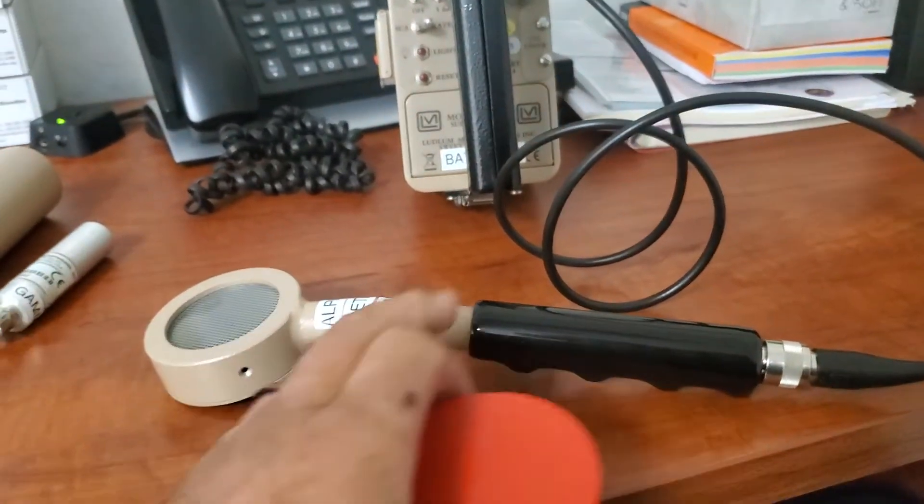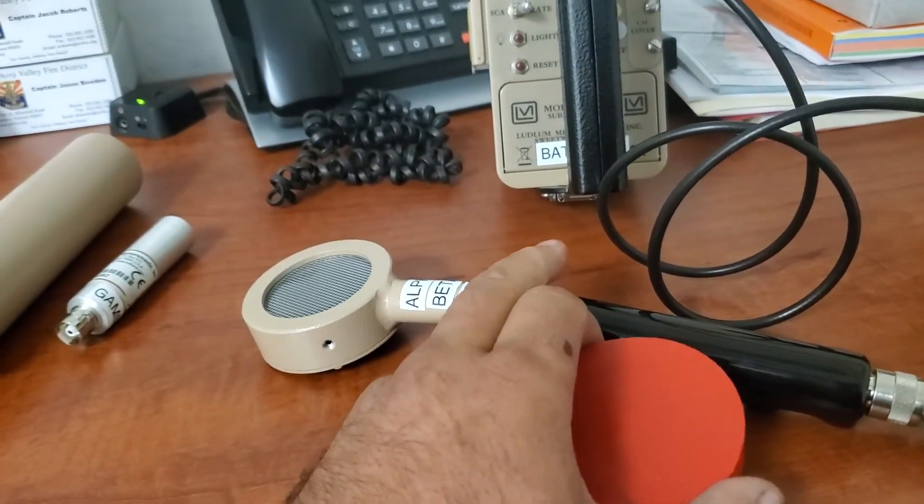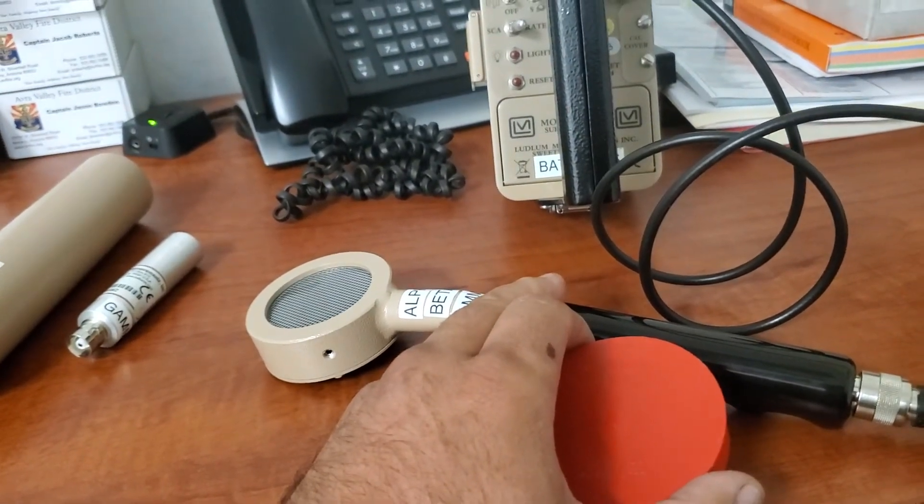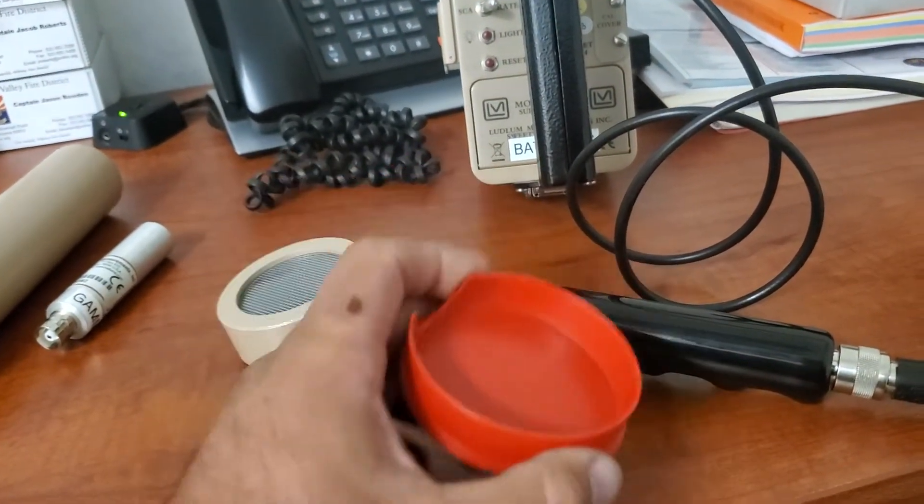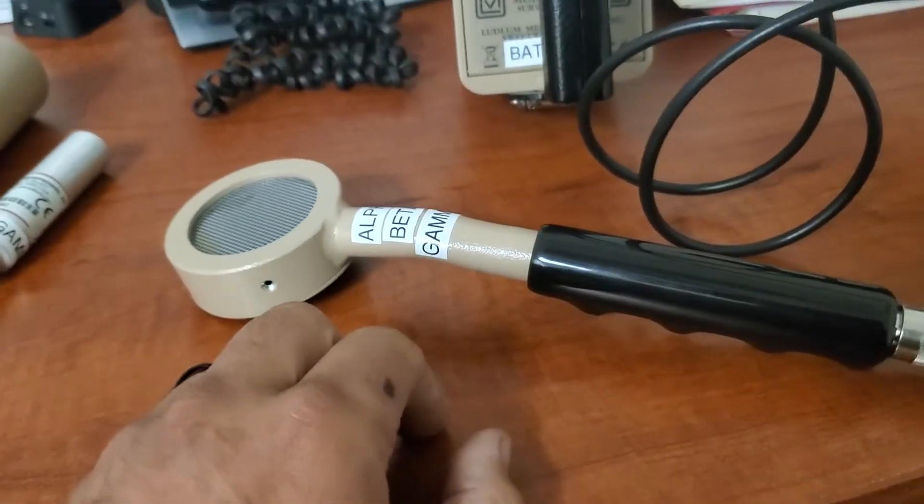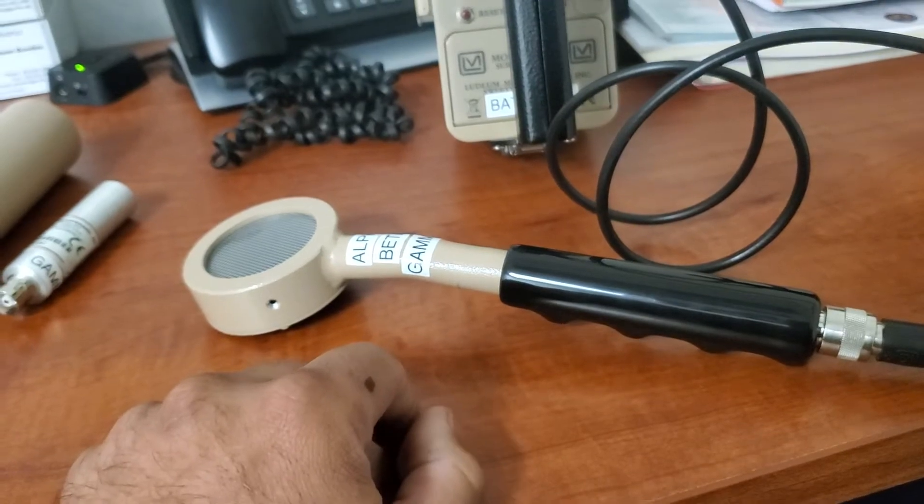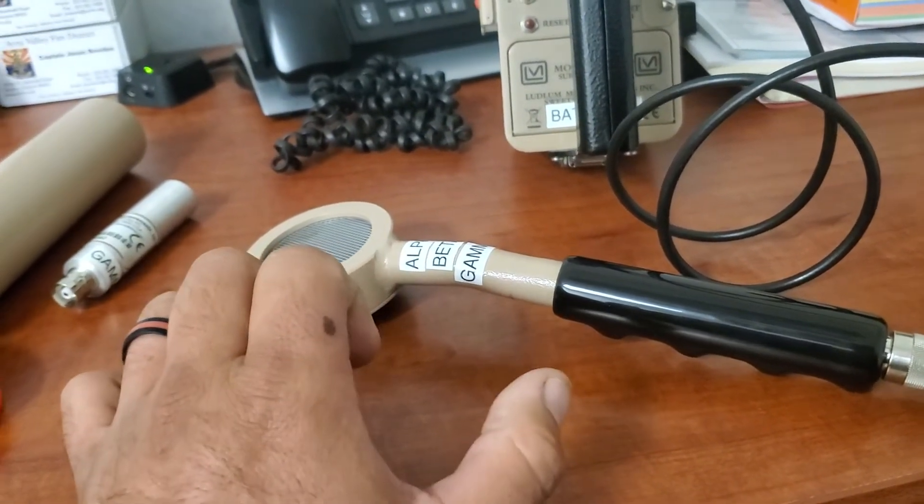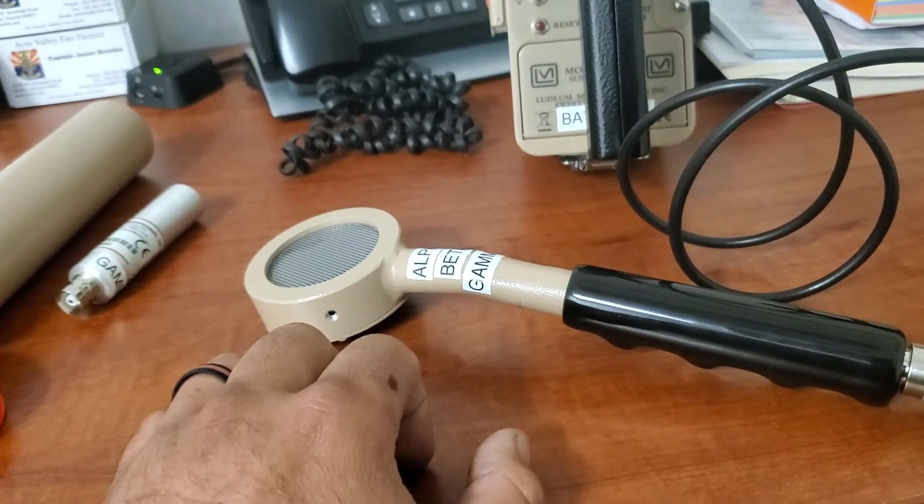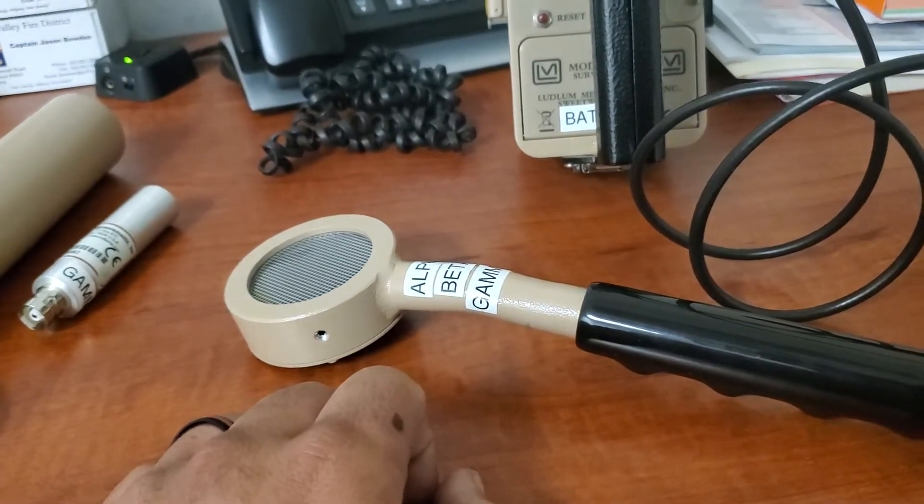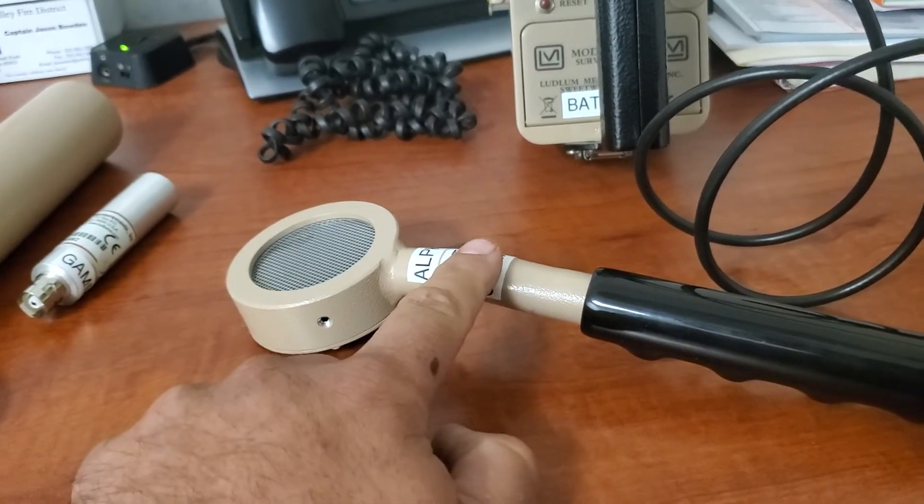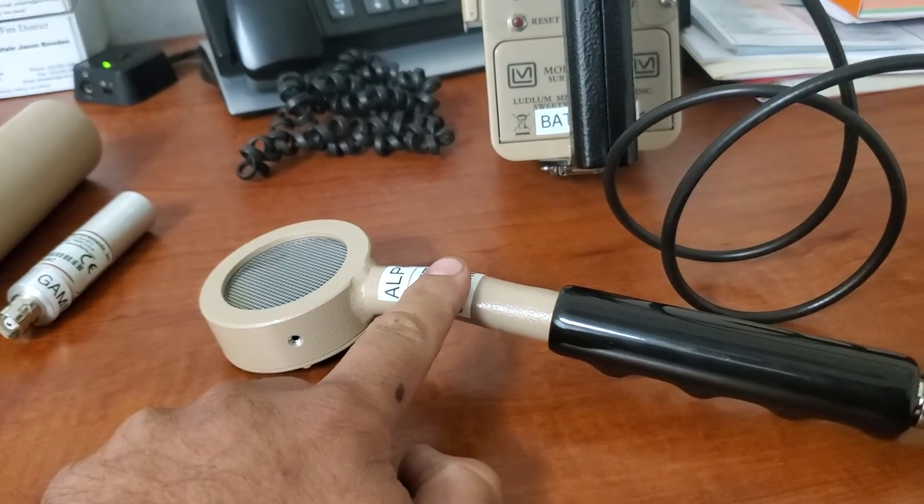The first probe we have here is the 44-9 GM pancake probe. Some people call it the Frisker. Comes with this little cap here to protect this little waffle. This probe is used to detect alpha, beta and gamma radiation. We use it primarily to detect contamination through decon or of an area. The range here is one count per minute to 100,000 counts per minute.